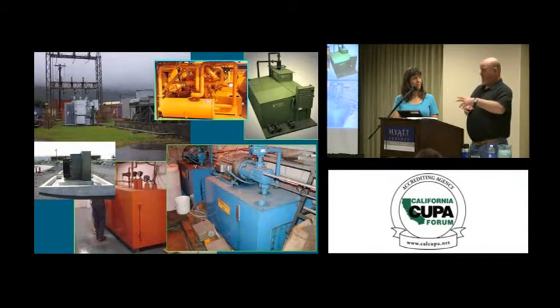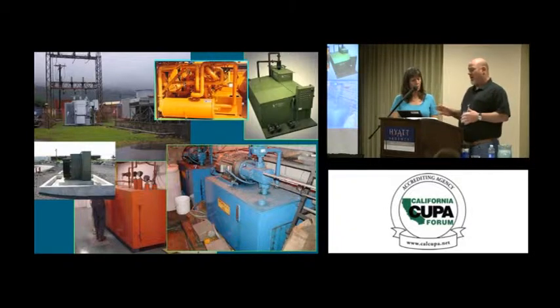So if it were above 1320, or if there was a storage container that took the reservoir at 60 gallons and the storage container at 1300, that's 1360, then that may require its own SPCC. You could do a Tier 1 plan for that. Would it be subject to sized containment, oil-filled manufacturing? No. The reservoirs, and I think I kind of am confused.